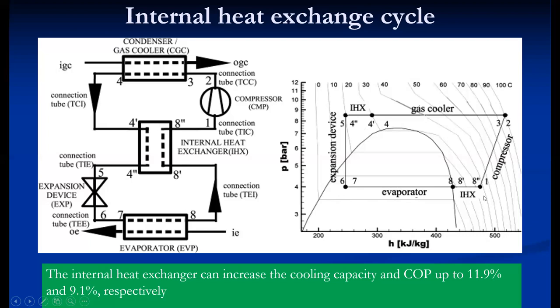If we put an internal heat exchanger between the cycle — similar to the liquid-vapor heat exchanger used in vapor compression cycles — the same type of heat exchanger used here increases COP by almost 10%. With the additional cost of only the heat exchanger, we can improve the COP by 5 to 10% when we use an internal heat exchanger.